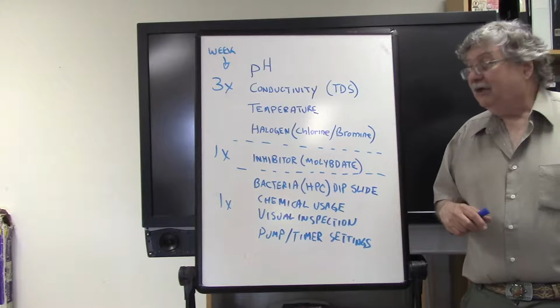The 4 things you need to test for every week are pH, which measures the acidity of water; conductivity, sometimes called total dissolved solids, a measure of the mineral content of the water, read on your controllers and test devices as conductivity; and temperature, which they want to know for your condenser or cooling tower water.